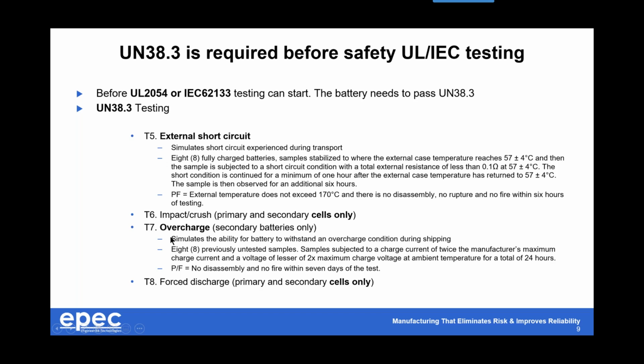And then T7 is overcharge. This one is normally a pretty severe test for a lot of packs. They look at the manufacturer's data sheet, and multiply the maximum manufacturer's charge current by 2, which is pretty severe, and they do the same with voltage. And then they hit this pack with this high energy. The pass-fail criteria is you do not want it to disassemble, no fire within 7 days. So they actually let these packs sit around.